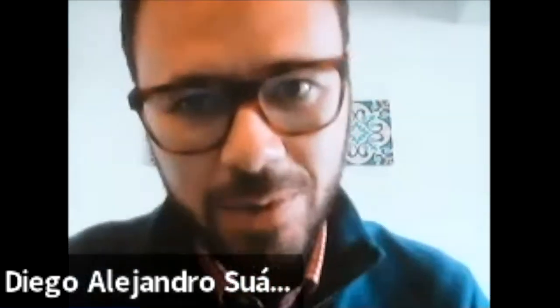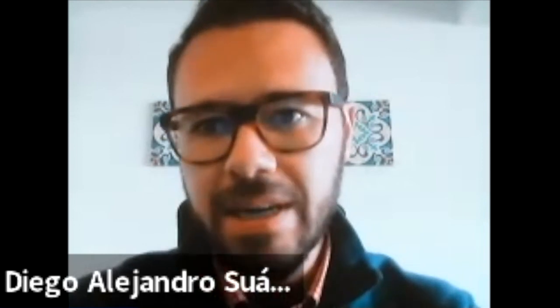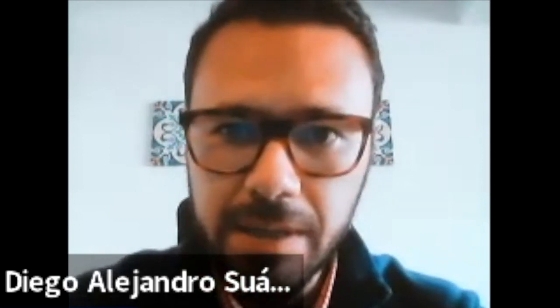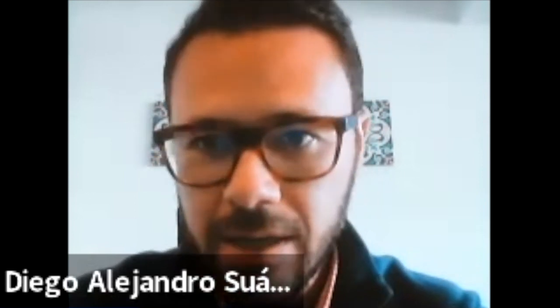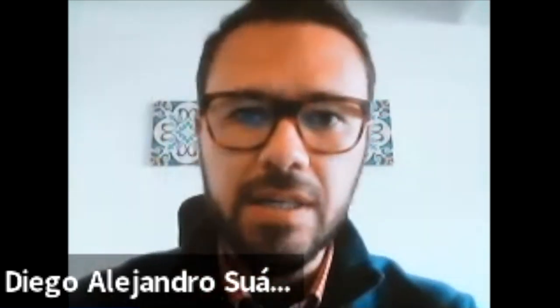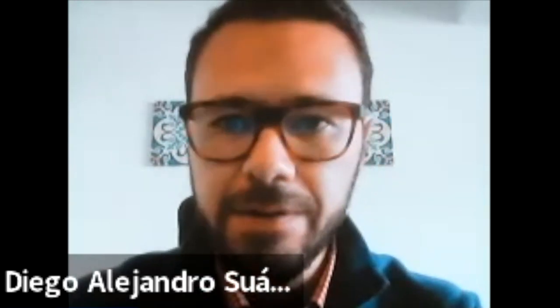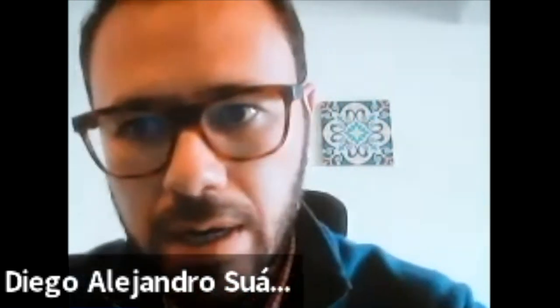He says, "Hi, Jim. Sorry, I'm coming in late and I may have missed something. Do you ever get pushback on floating MRI room floors with metal springs from MRI manufacturers? If so, what can you offer them to address concerns?" We do, and on that one project I mentioned, that was a concern. And in discussing it with the MRI manufacturer, they realized that we could work. Initially, they said no steel in the room at all, but they had such a terrible vibration problem we had to come to some compromise.